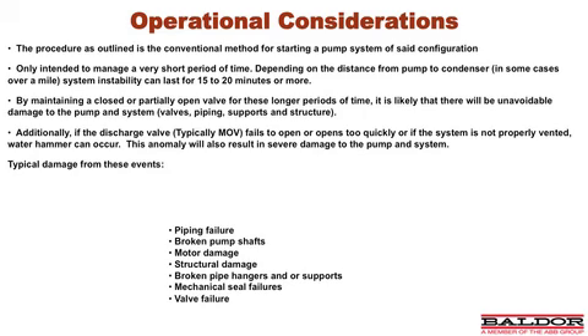The flow is being restricted in the pump, resulting in internal recirculation, and the pump is shaking and shuddering during this process, causing excessive vibration and stress on the pump, the motor, the intake structure, the piping hangers and supports, as well as the valve. This startup sequence is only intended for a very short period of time.